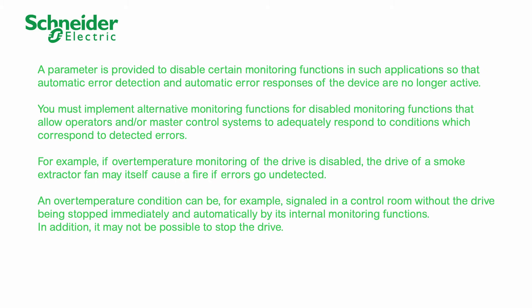A parameter is provided to disable certain monitoring functions in such applications so that automatic error detection and automatic error responses of the device are no longer active. You must implement alternative monitoring functions for disabled monitoring functions that allow operators and/or master control systems to adequately respond to conditions which correspond to detected errors. For example, if over-temperature monitoring of the drive is disabled, the drive of a smoke extractor fan may itself cause a fire if errors go undetected.